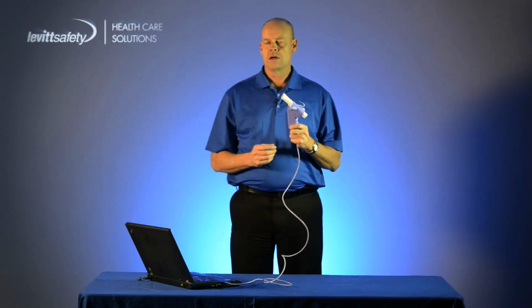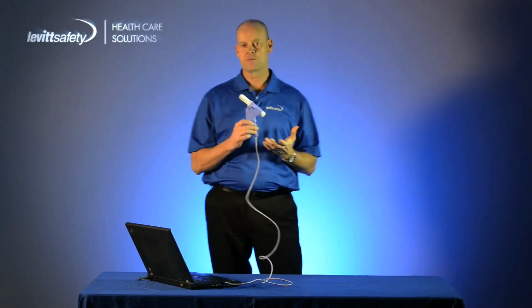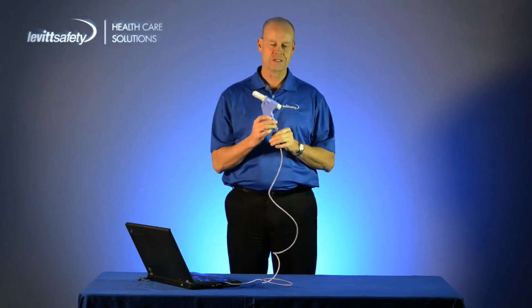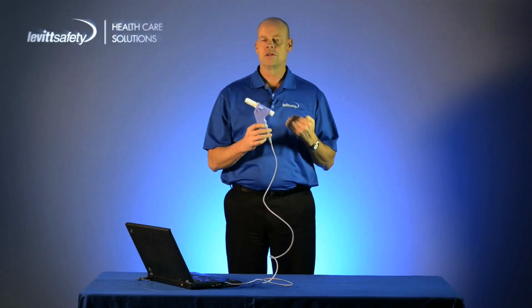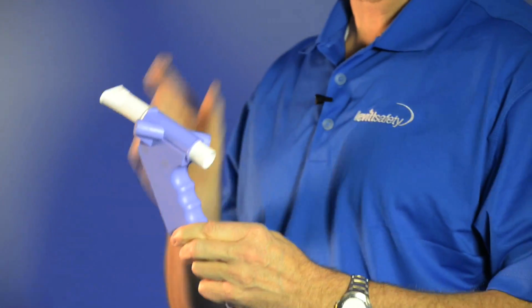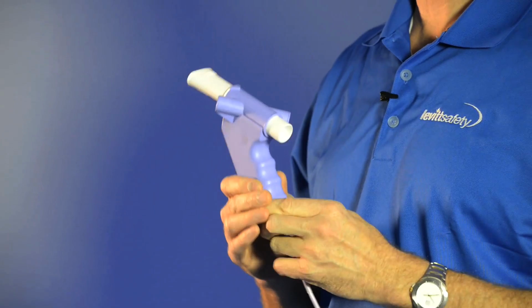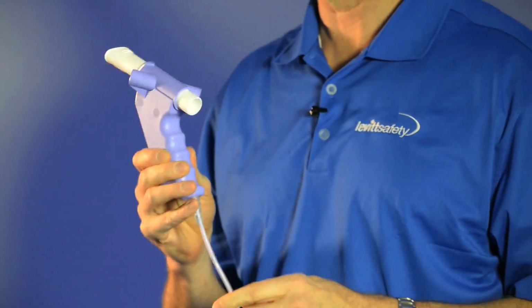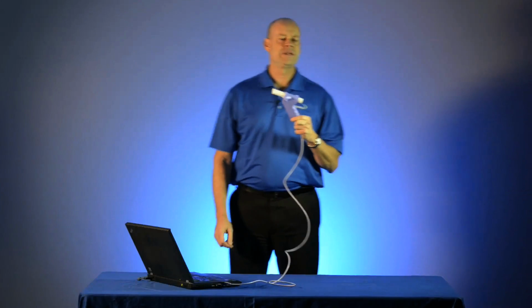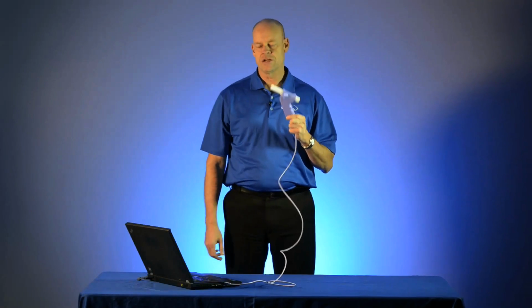The NDD Easy On PC Spirometer uses ultrasonic flow principles for its measurement of the airflow when the person blows into the device. And it's still recommended that you always check your calibration with a standard 3-liter calibration syringe, which is an accessory that's available with this. So that's a complete demonstration of the NDD Easy On PC Spirometer.